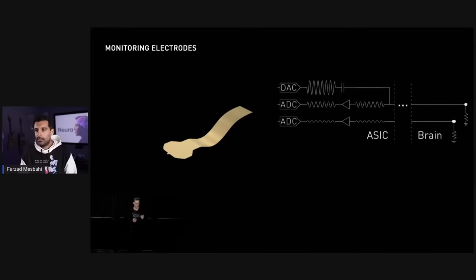Capturing good quality neural signals requires intact, low impedance electrodes, and this is also something we monitor very closely with dedicated circuitry on the neural sensor. So how do we do this? We do this by first using an onboard DAC to play a test tone on a single channel. Then we record using our ADCs simultaneously, the response signal on both that channel and physically adjacent channels.